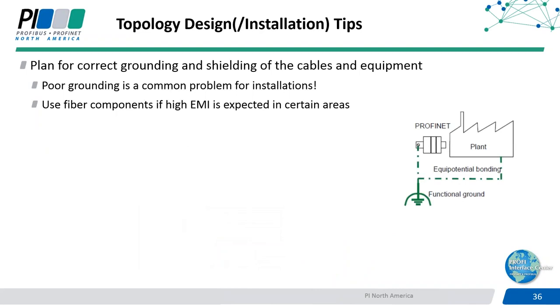Now, and probably even more important than that tip we have for the topologies, is a plan for correct grounding and shielding of the cables and the equipment to protect against electromagnetic interference. This is a really common problem that is often overlooked during design and installation. And if motors and drives are used, it is even more critical to properly shield those types of components.